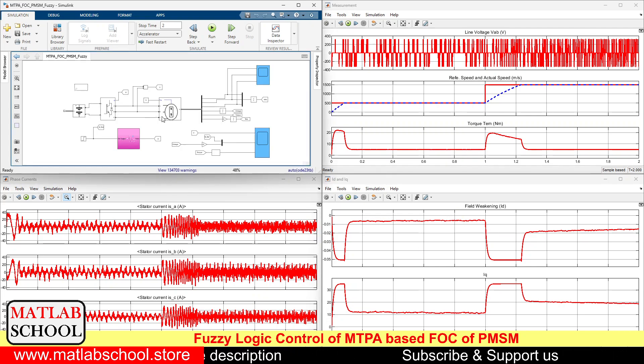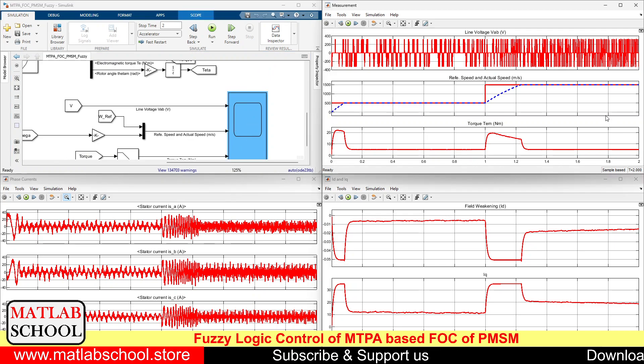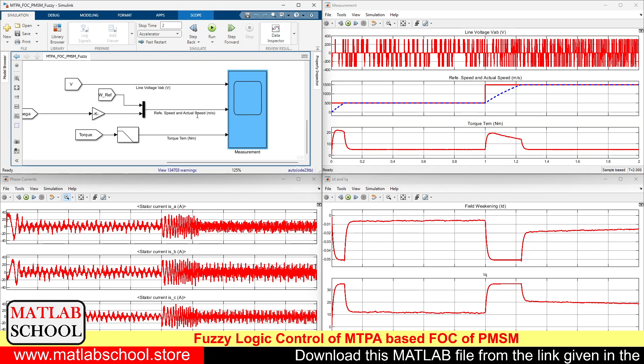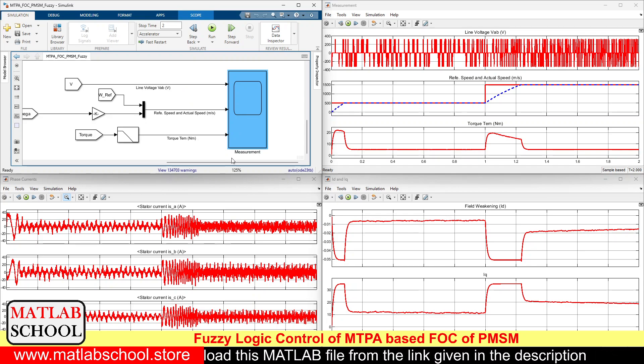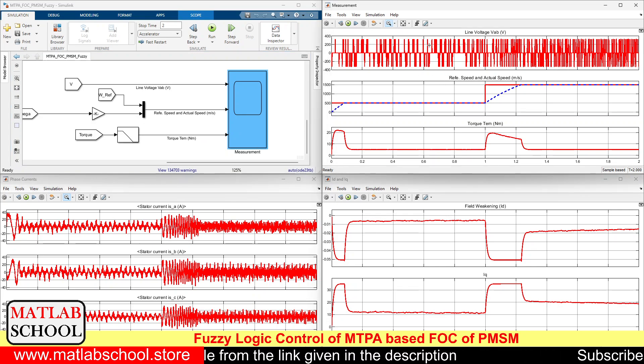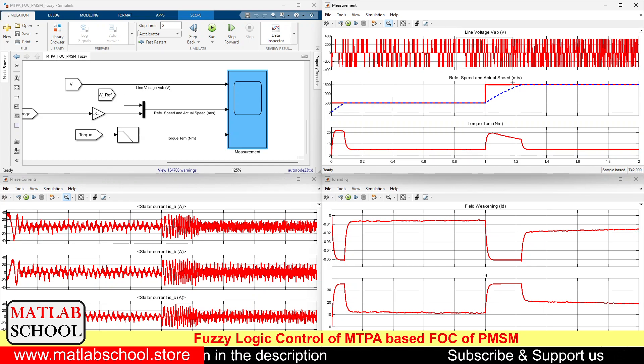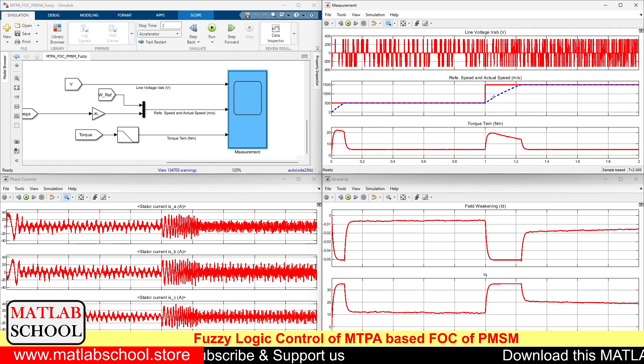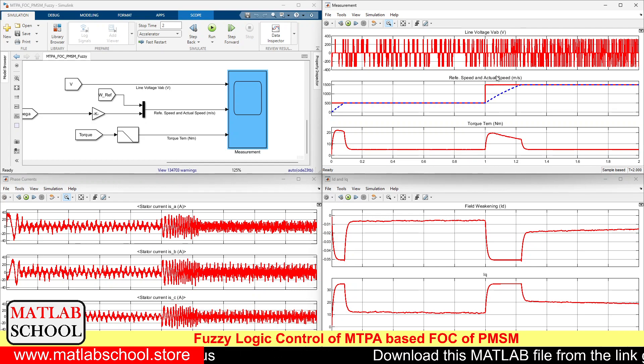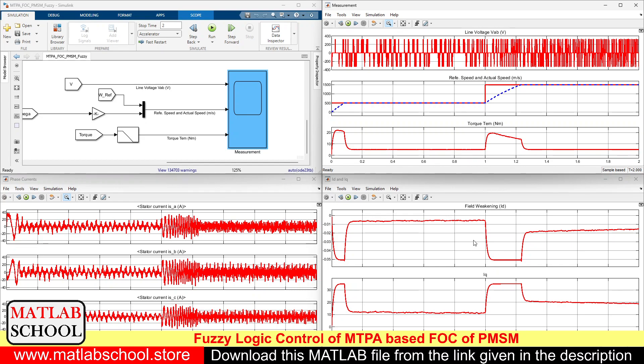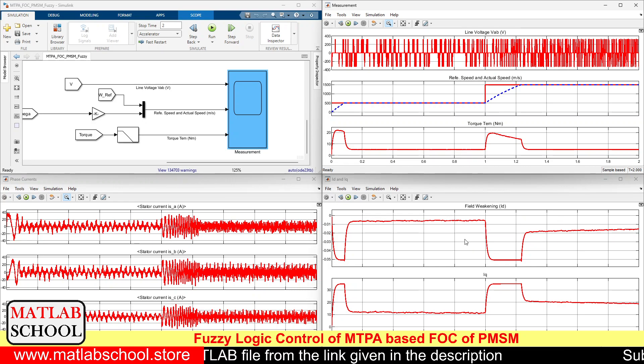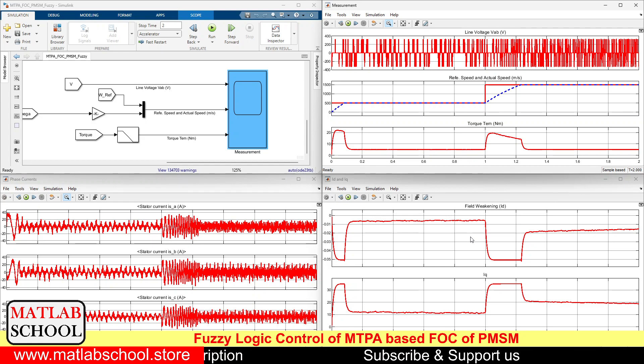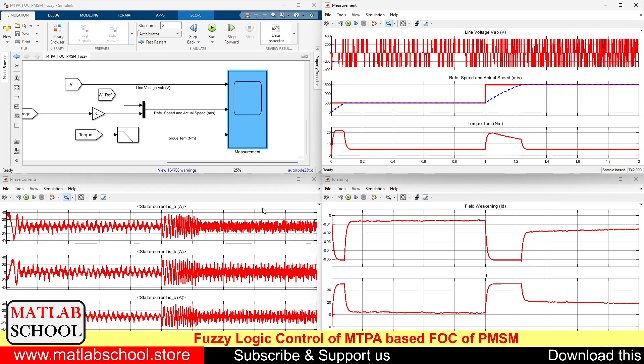These are the different outputs. If you click this scope, it will open. Through this scope, we are measuring three things: line voltage, reference speed, and actual speed, and finally the torque. This is the line voltage across phase A and B. The red one is the reference speed and the blue one with dots is the actual speed. Here we have field weakening happening — when the speed goes above 750 RPM, a negative current reference is given, which makes the motor run above 750 RPM. These are the corresponding stator currents.